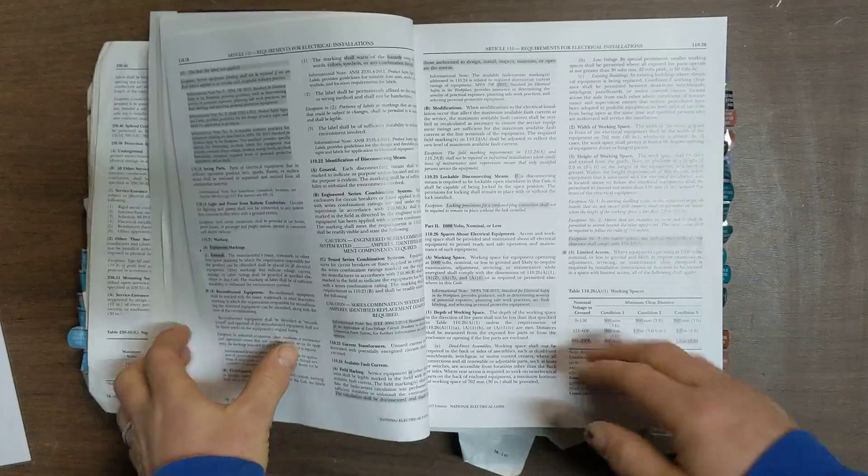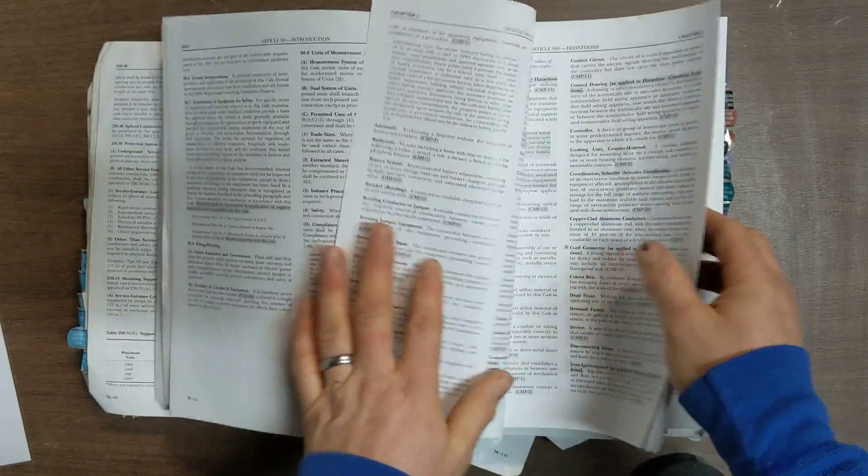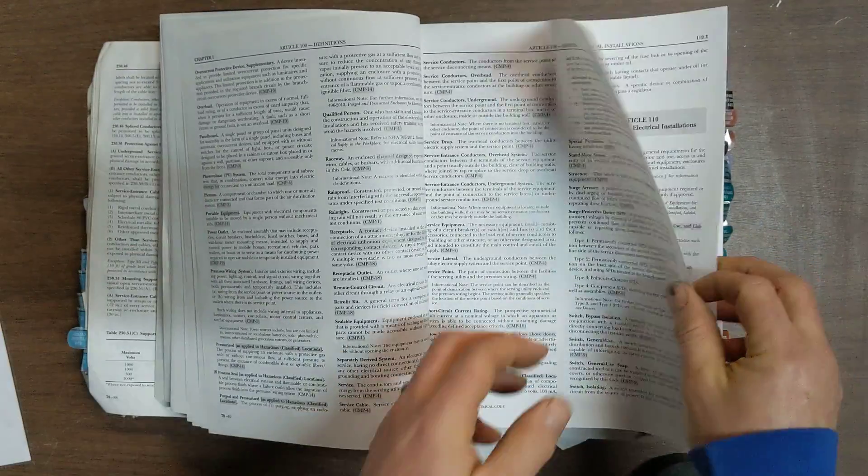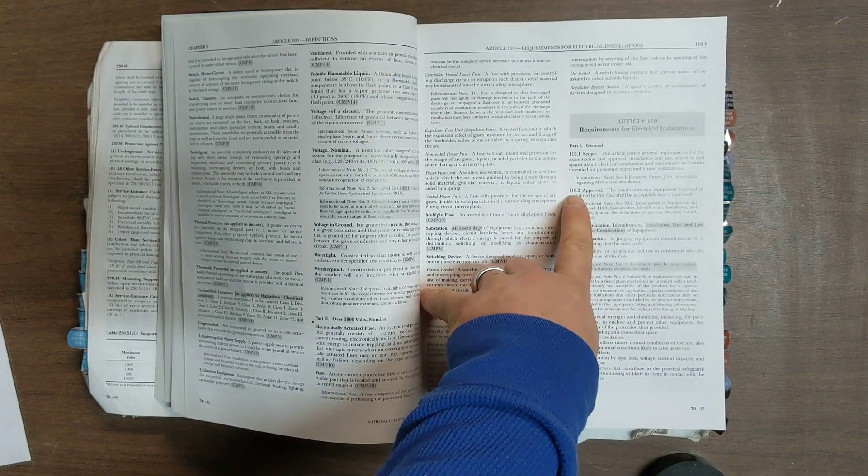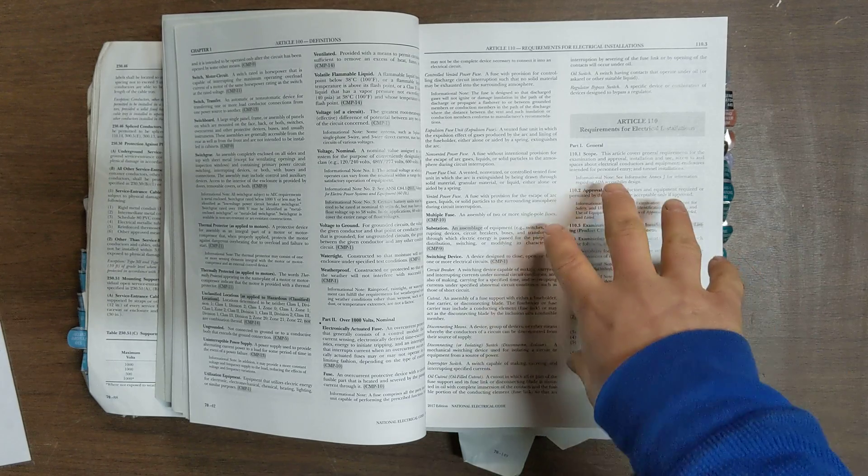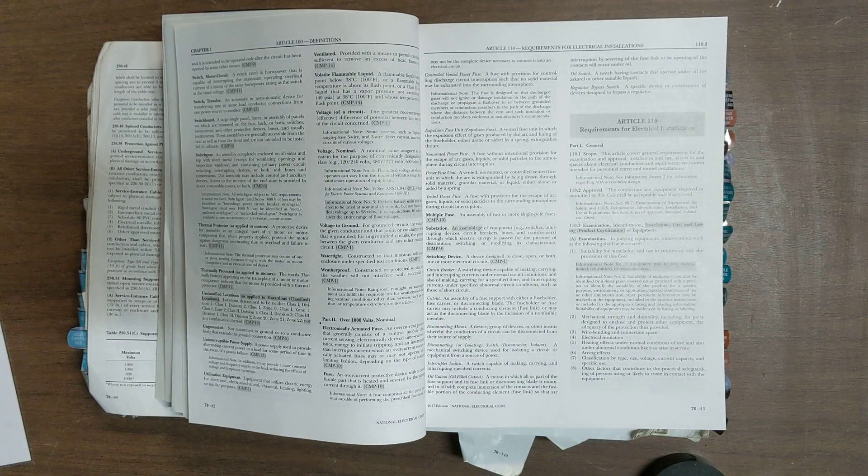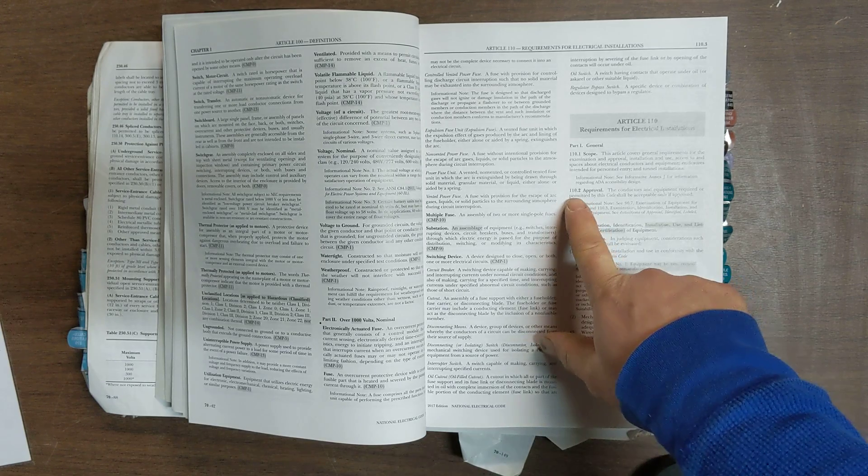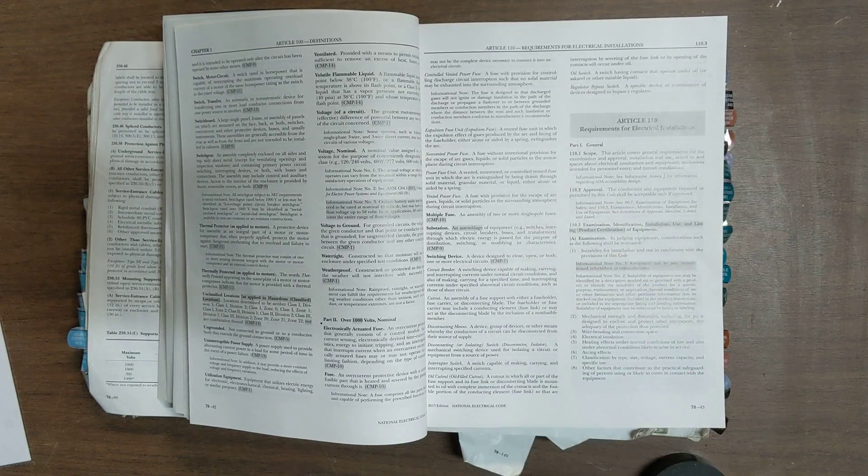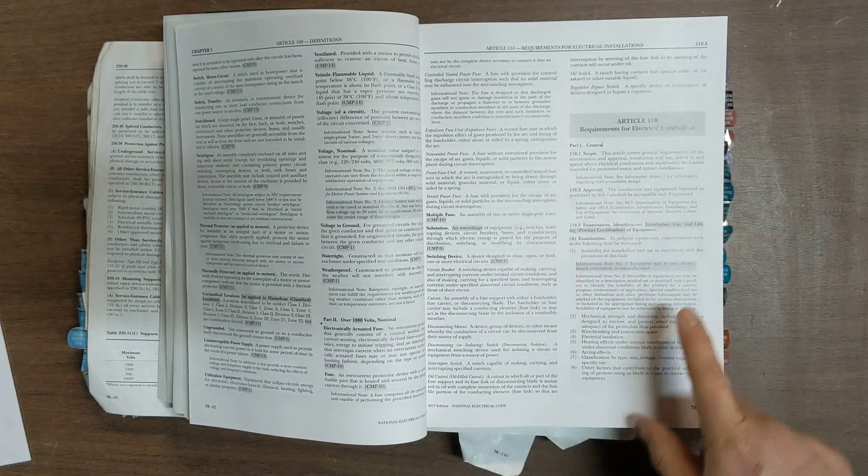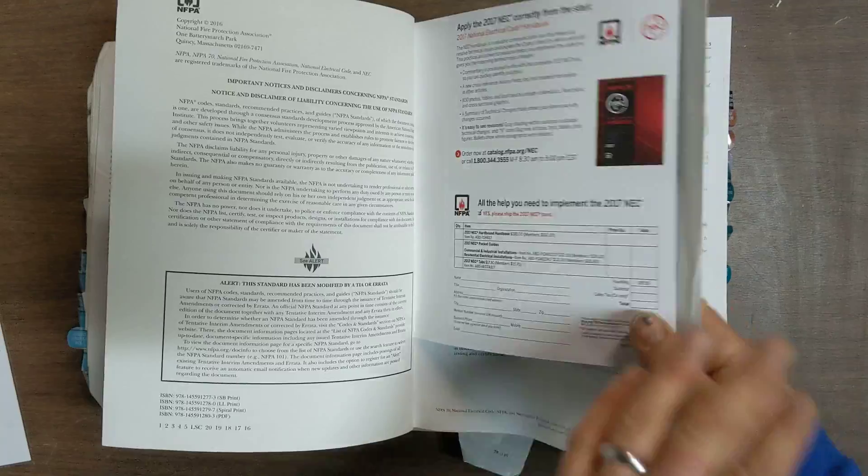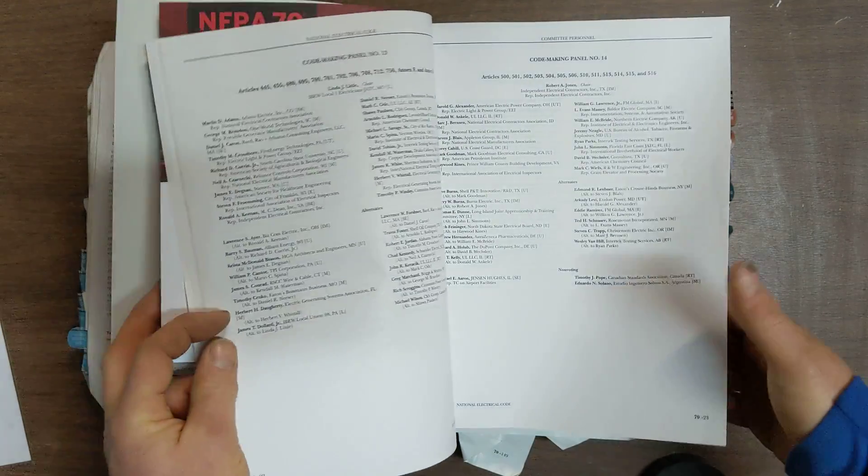So you move through here. Let's go to article 110 and I'll show you something neat. It could help you in testing, but it can also help you just in your electrical career. That most of the time when you get to the beginning of an article, we'll go to 110. If you go to the .2 section of that article, that is going to be definitions that only apply for that article. So 220.2, 230.2, it applies to most of the code sections that the .2 section is going to be for definitions that apply only to that section. You cannot take this definition of approval and apply it in 220. You cannot take 220's definitions and apply it to article 110, but the definitions listed in article 100 are code-wide. They apply to the entire codebook.